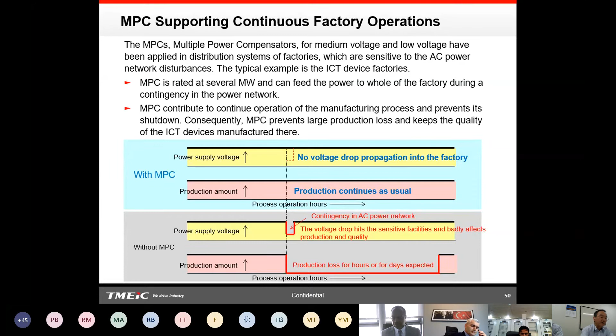Page 51. Normally, the MPC feeds the power to the factory directly through the high-speed AC switch. In case very sensitive loads are connected to the system, sometimes a very quick cut-off is required. The high-speed semiconductor switch will be applied. The mechanical switch offers a cut-off time of typically 1 cycle, but utilizing the high-speed semiconductor switch offers a cut-off time of several milliseconds, a very quick cut-off, with no effect to the load from the AC power network.